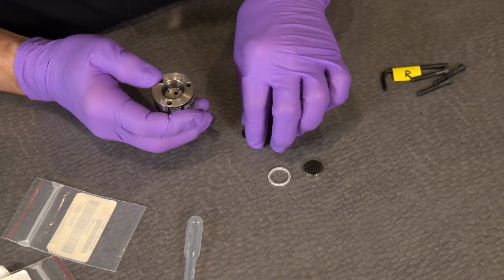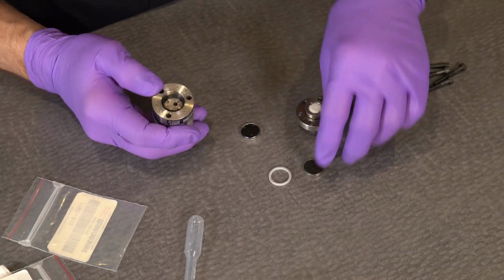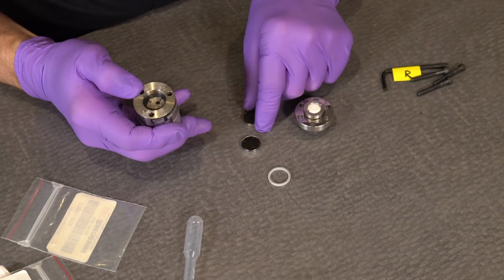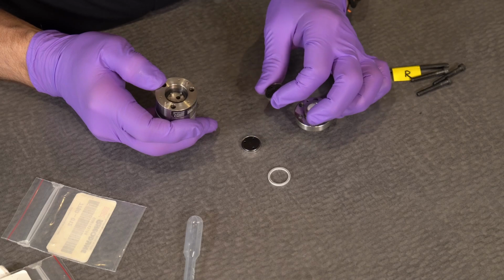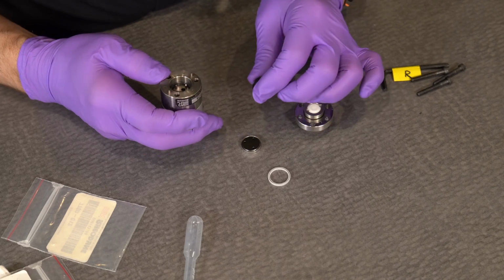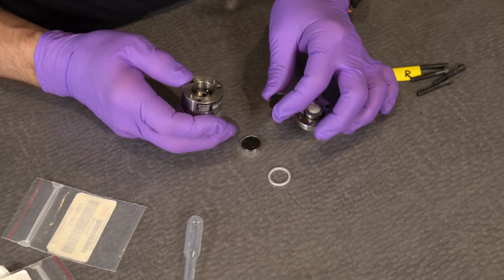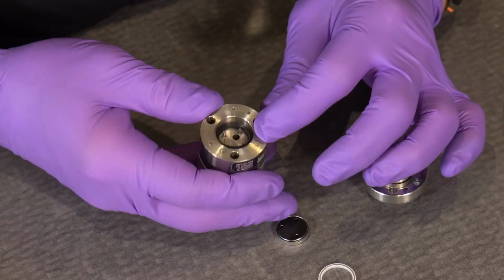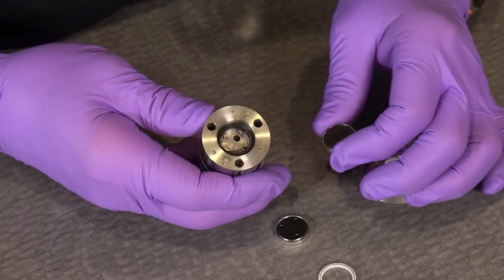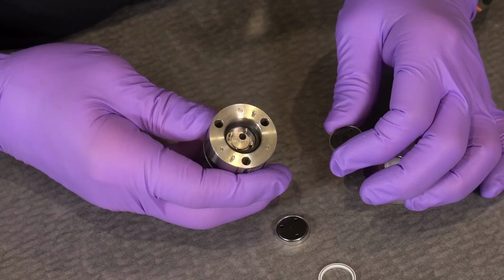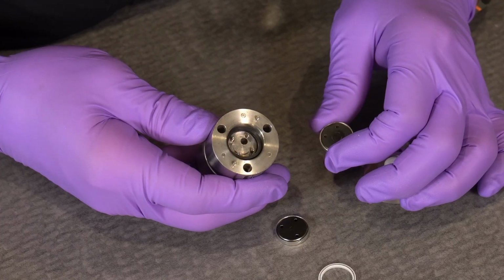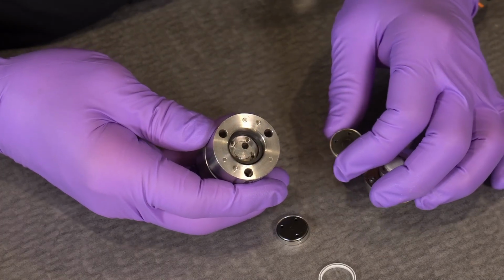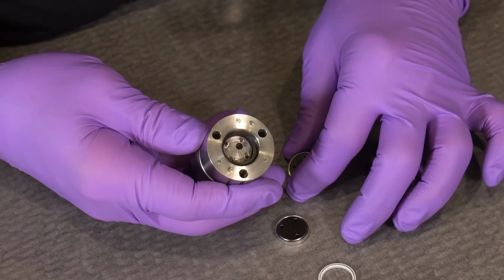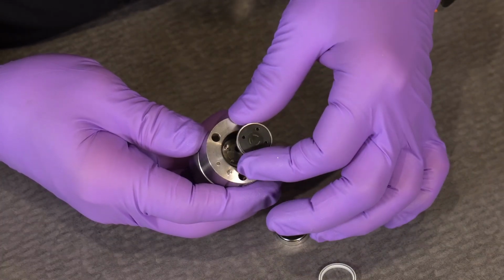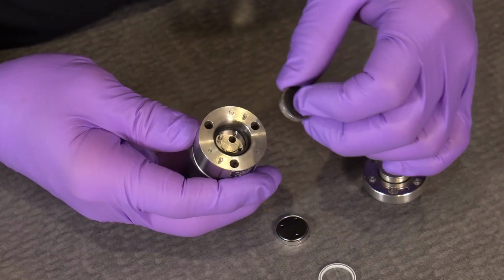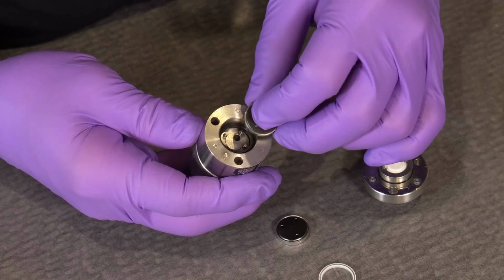And then we're going to have our rotor seal. So again, that's the part that's going to wear out. I'm going to put the same one back in, because if you look at the little pegs inside there, there's 4 pegs. They're not a complete square. They're a little bit of a, I don't know, is it a parallelogram or a trapezoid maybe. So it'll only fit those 4. So that's the nice thing about these valves, is you can't put them together the wrong way.